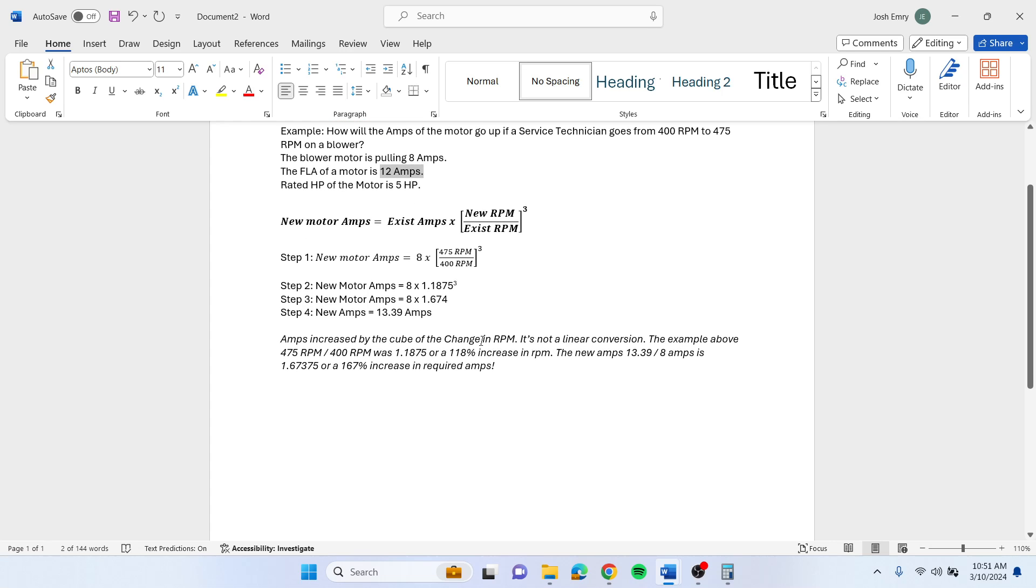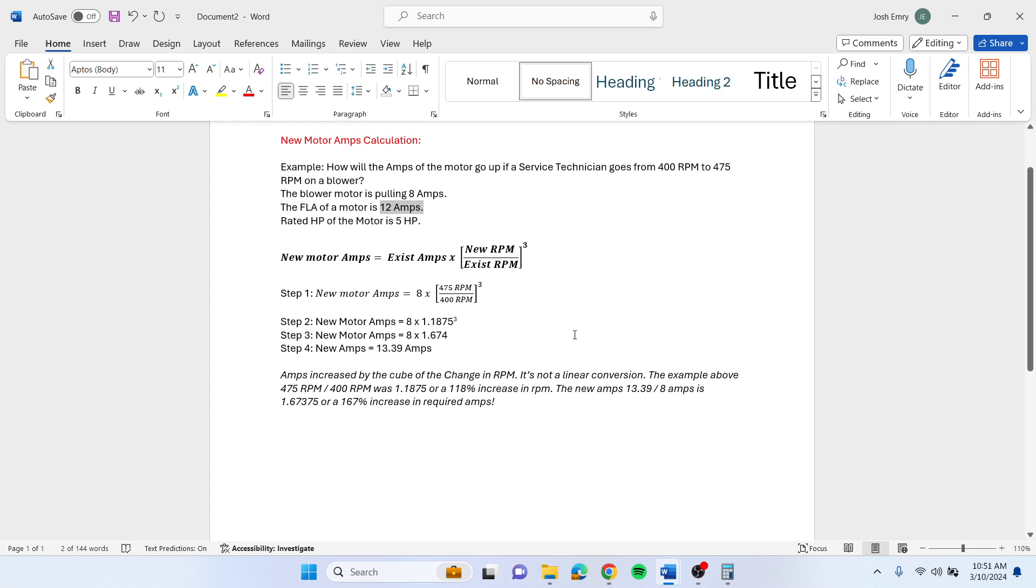One thing to keep in mind is it's not a linear conversion. If you go up in RPM, you've got to figure that your amps increase by the cube of the change in the RPM, so it's not a linear conversion.